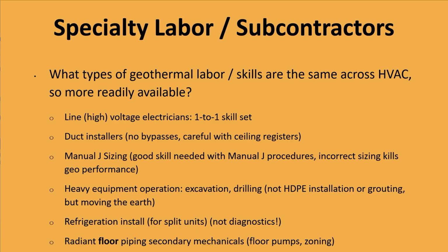Manual J sizing is technically the same for geothermal as anything else. The caveat is that most HVAC contractors are a little sloppy with their sizing. For new construction it's different, but there are lots of rules of thumb people use. If you get somebody skilled at Manual J, they can do it whether it's geothermal or not. The load is the load before you've selected the heating and cooling system, as long as they've done an accurate load. Lots of contractors are afraid they don't know how to do an accurate load, so they add extra tonnage.